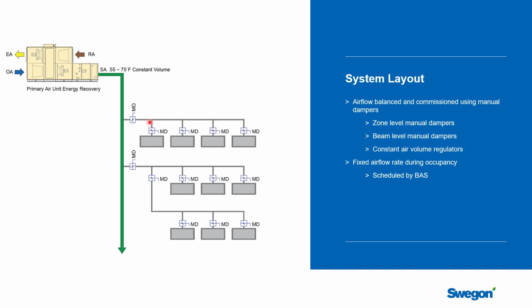In addition to the primary air that's delivered to the beams, you would also have chilled water and possibly hot water, depending on the system design. Now, this is a constant volume system, meaning that it is going to run at its design airflow rate whenever the system is in operation. This is usually controlled by the building automation system. If the building is going to start at 7 o'clock in the morning, at 7, the building automation system will start the unit up and it will run at its design airflow rate all during the operating hours until night's shutdown.